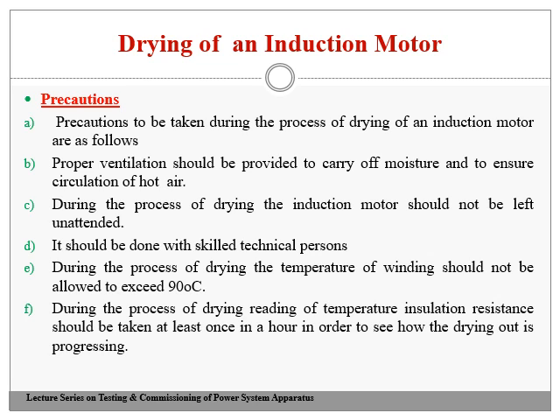During the process of drying, the temperature of the winding should not be allowed to exceed 90 degrees centigrade. That is one of the precautionary measures to be taken here. At any time during the drying process, the temperature inside the induction motor or winding should not go beyond 90 degrees centigrade.